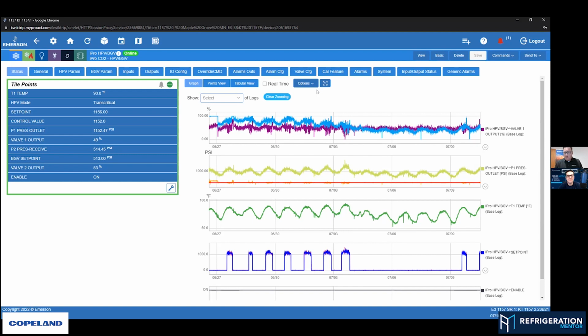And then there's another mode where if the vessel pressure, so the pressure in our liquid receiver, is getting too high, we will try to close that down again and try to stack refrigerant into the gas cooler, because our liquid vessel has got too much pressure that we can't use liquid off it. We're creating too much vapor.